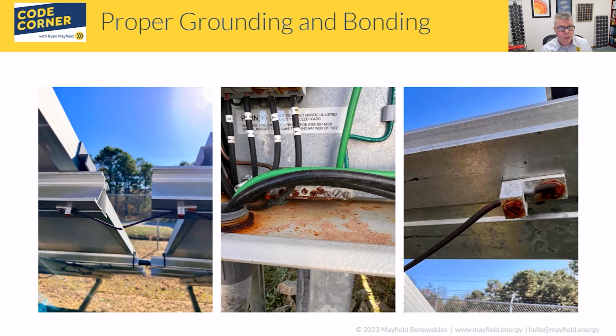We have a jumper between those, but if they're not properly maintained, the far right there is more of a close-up of that. You can see where that ground lug, the set screw, is actually rusting out, and so that would be highly suspect. Is that a good bond still? This screw that is connecting it to the rail is rusting out, so questionable on even having those connections made.